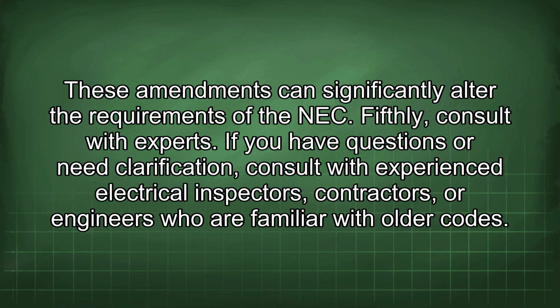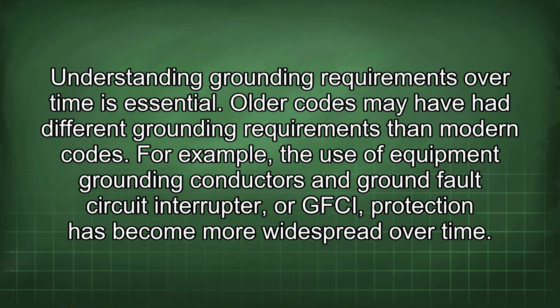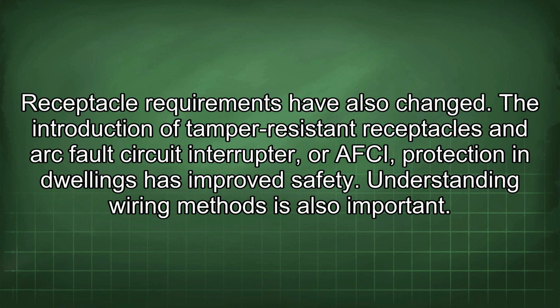Fifthly, consult with experts. If you have questions or need clarification, consult with experienced electrical inspectors, contractors, or engineers who are familiar with older codes. Understanding grounding requirements over time is essential. Older codes may have had different grounding requirements than modern codes. For example, the use of equipment grounding conductors and ground fault circuit interrupter, or GFCI, protection has become more widespread over time. Receptacle requirements have also changed. The introduction of tamper-resistant receptacles and arc fault circuit interrupter, or AFCI, protection in dwellings has improved safety.